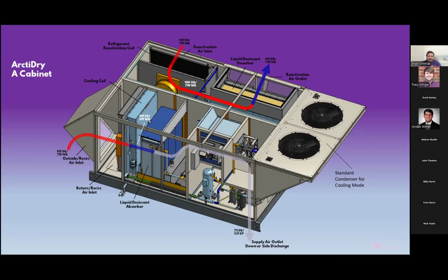So we're going to take outside air, we're going to pass it through our reheat coil, then we're going to send that hot air over the desorber pad. And what the desorber pad is for is, again, we're taking that diluted desiccant, it's flowing down through that pad, we're providing heat across that pad, essentially acting almost as a swamp cooler, where you are providing more humid and cooler air on the other side of that pad, but we're evaporating that moisture from the solution itself. The more heat through that hot gas reheat coil that we provide, the more concentrated we can get the desiccant.